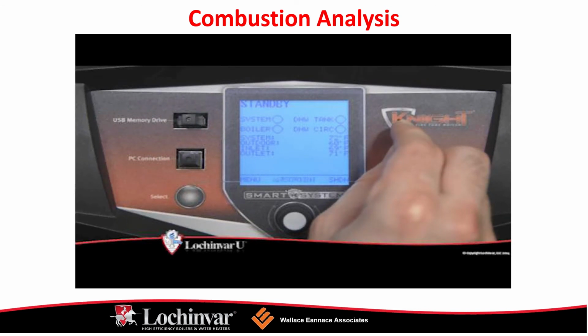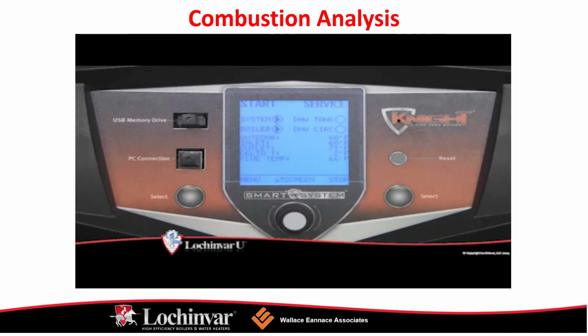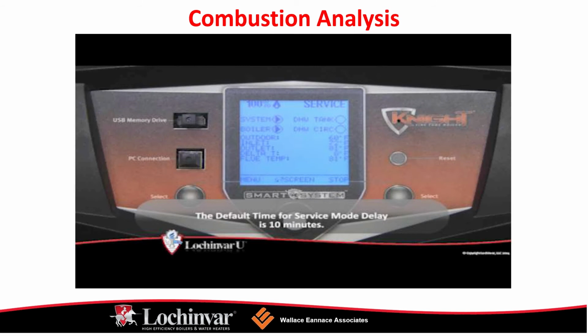These are pretty much the ranges we want to see when it comes to natural gas or LP on your CO2 and your O2. CO2 for natural gas units, 8% to 10% is a normal reading. On O2, 3% to 6.5% is a normal reading. And on your propane gas models, the CO2 we like to see 9 to 11, and on the O2 around 4 to 6.9. All these readings are taken at high fire.